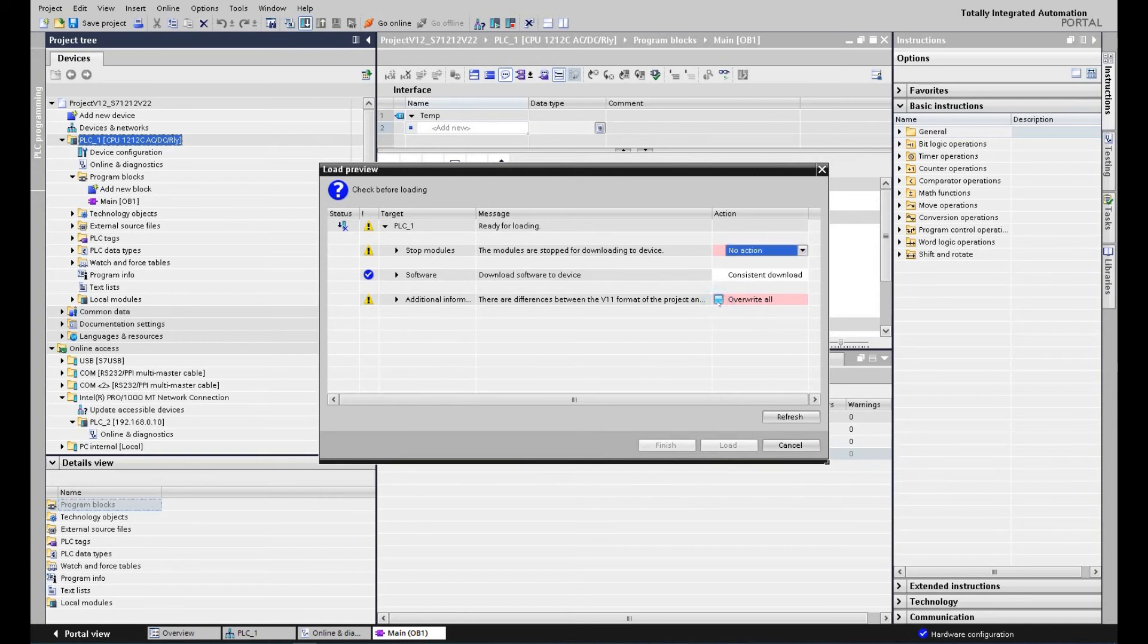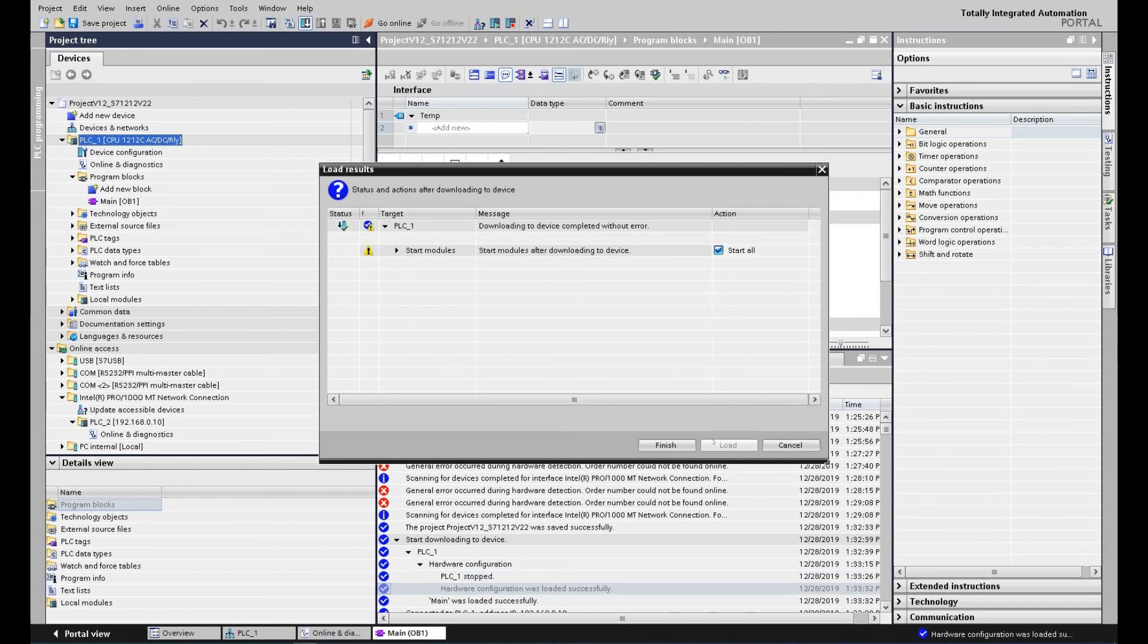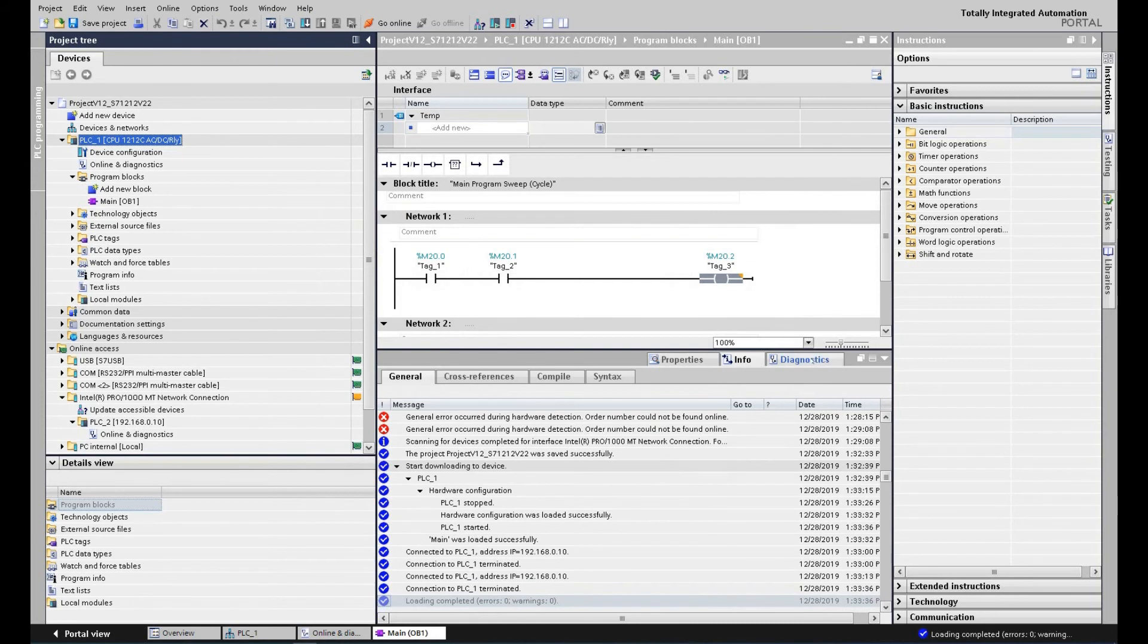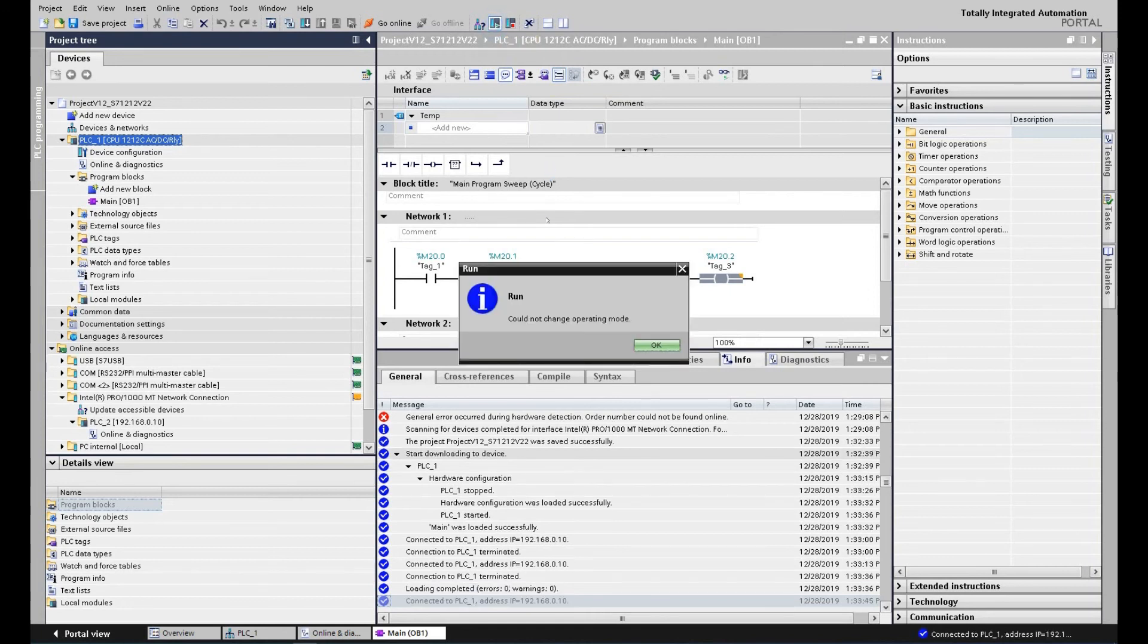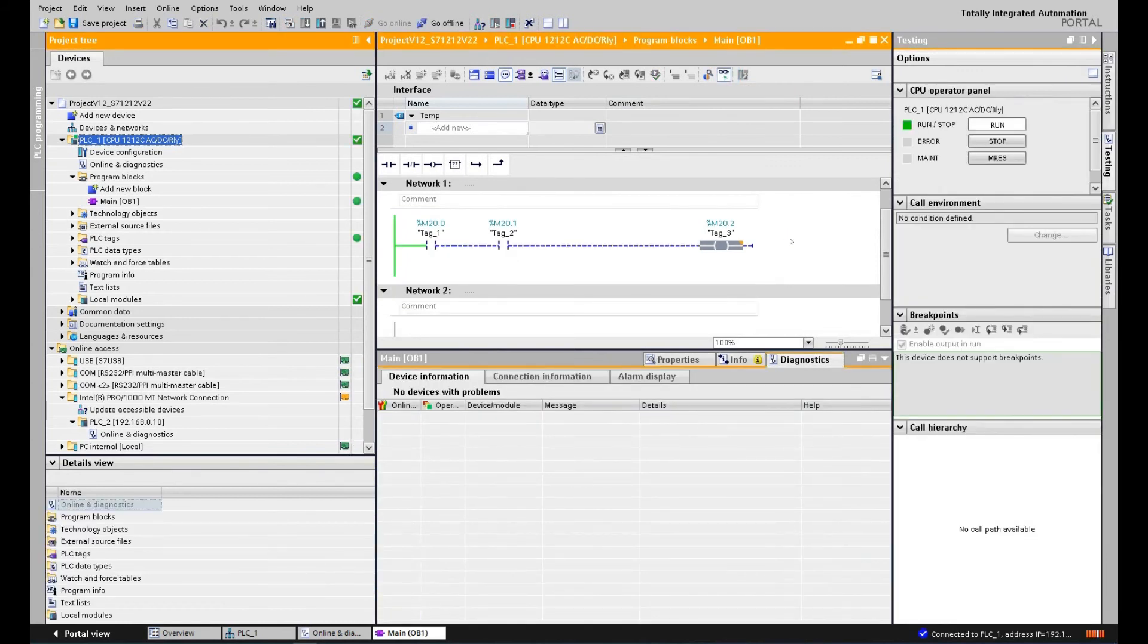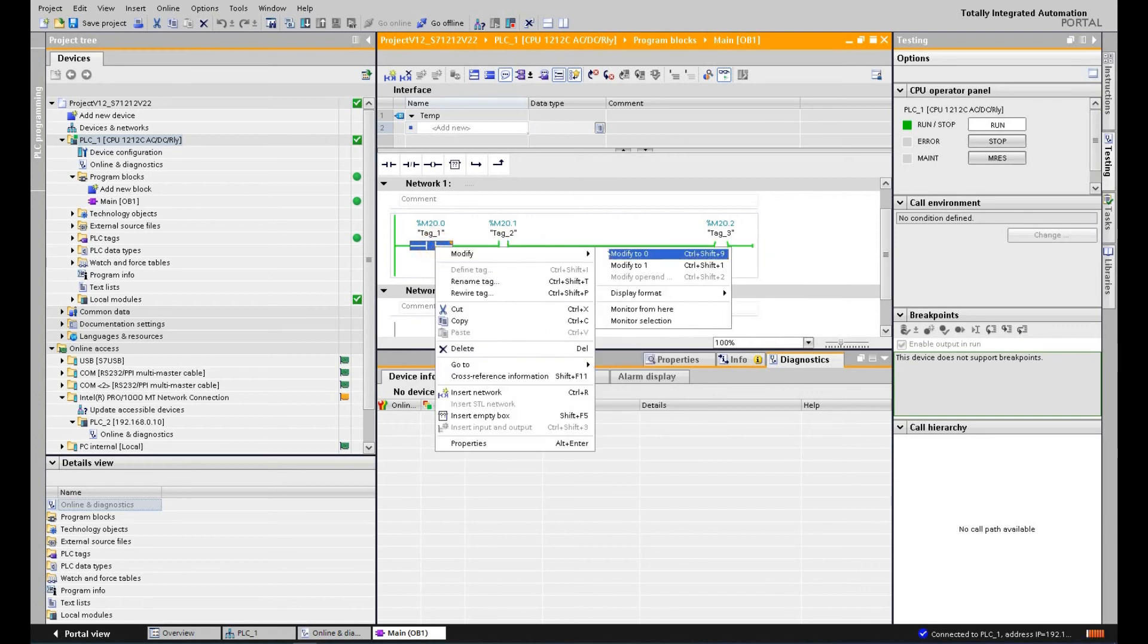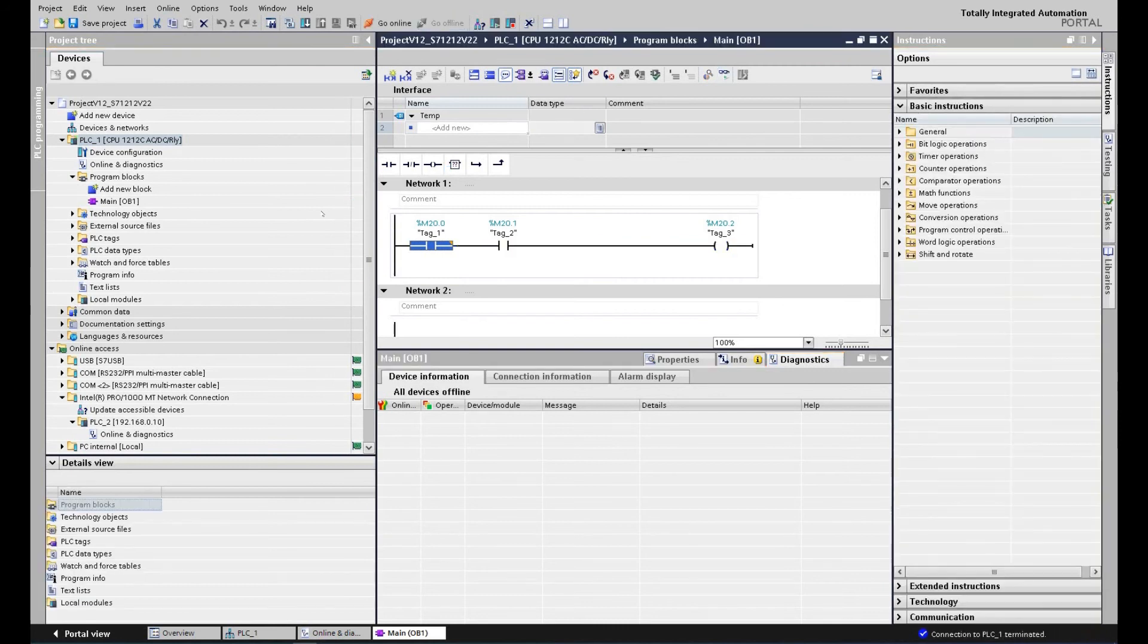So here, because we need to download the controller, plus the hardware and the software, so the controller need to restart it. Click load, and stop the controller overwrite all, and then restart the controller. OK, now the controller is already in run mode. Let's test the communication, and let's test the logic to see if the version 12 TIA Portal can test the controller. We can see that everything shows fine. So the version 12 can communicate with the actual controller, and we can program using version 12 in Windows 10.